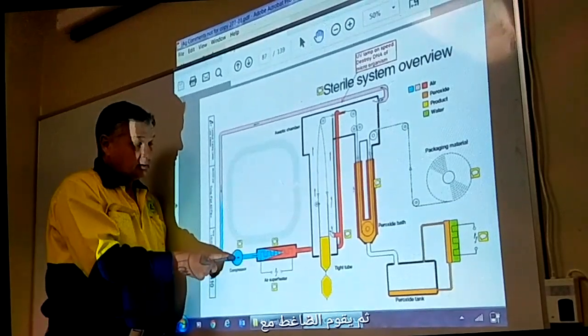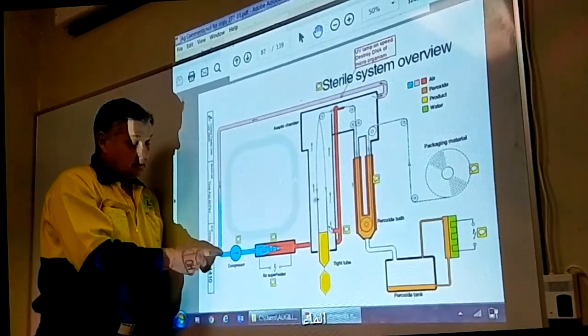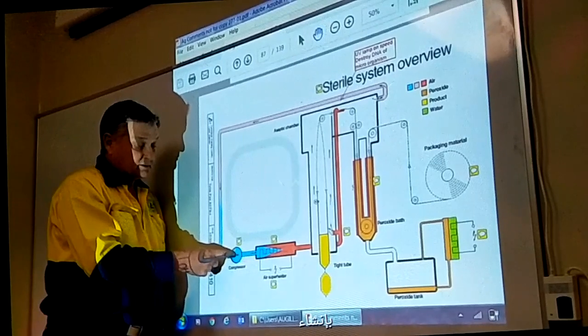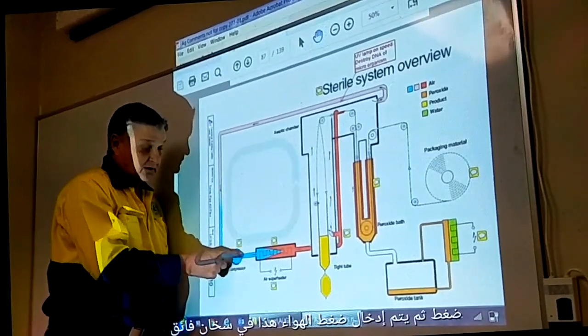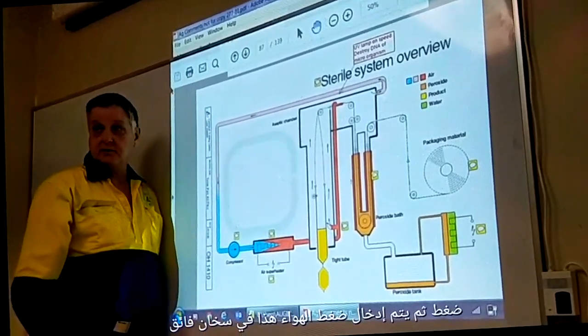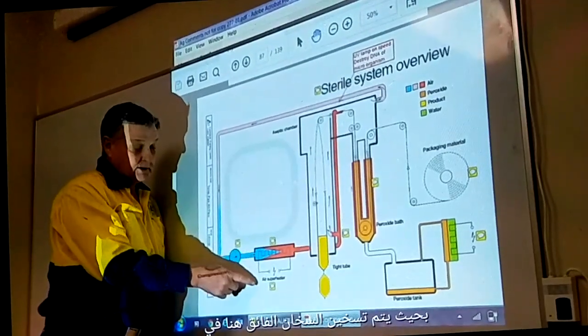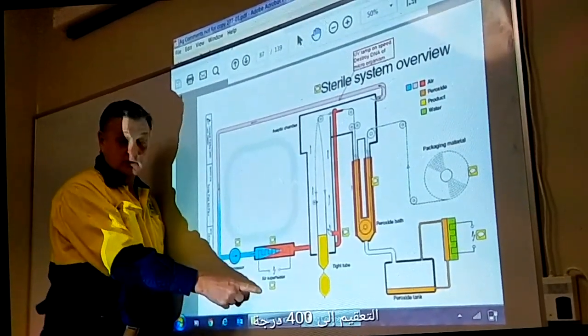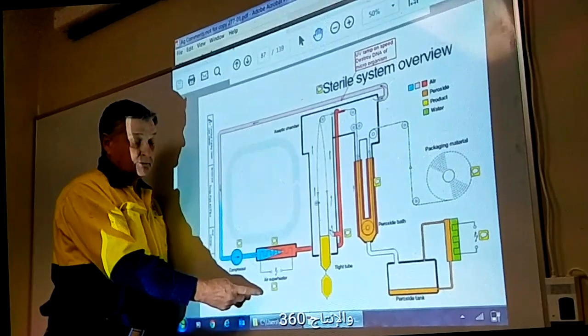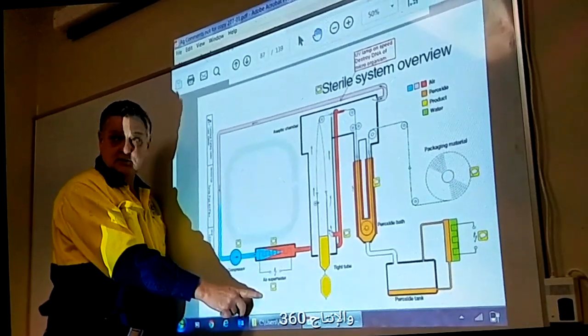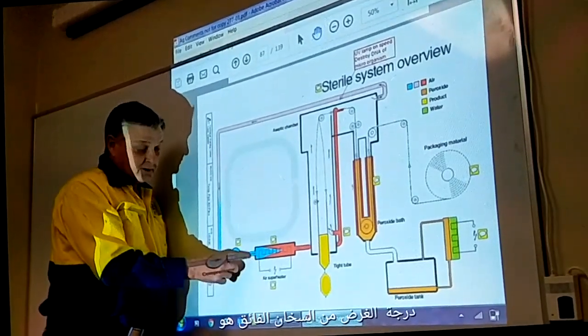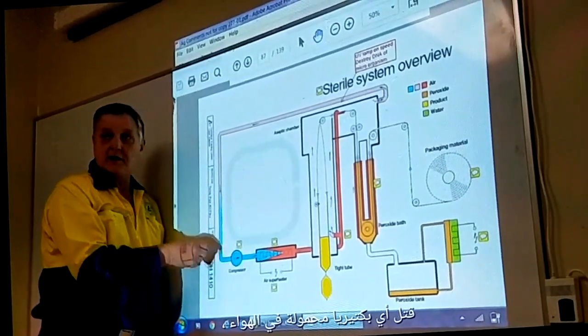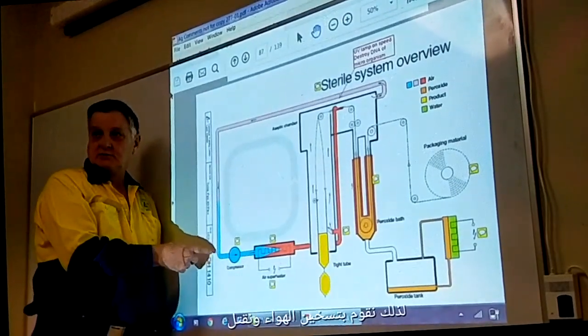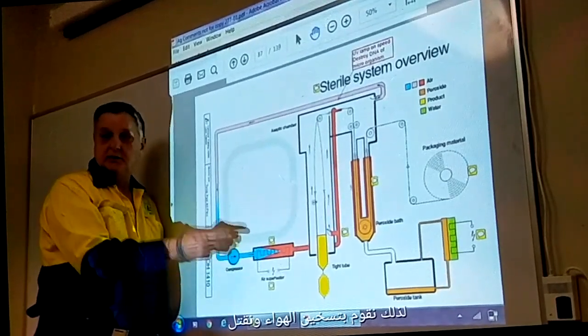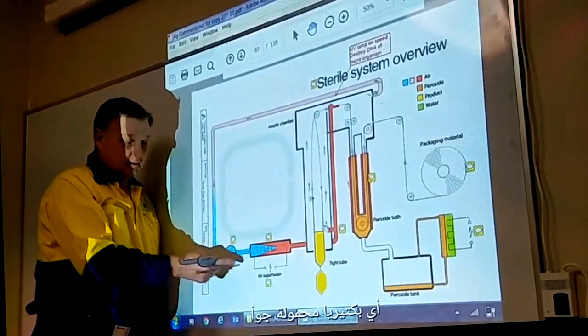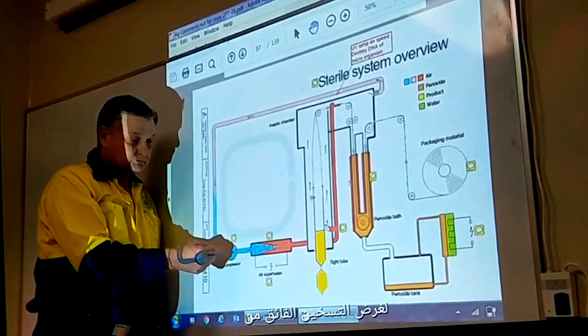So then the compressor, together with water, creates a pressure, and then this air pressure is fed into a superheater. So the superheater here heats up in sterilization to 400 degrees, and the production 360 degrees. The purpose of the superheater is to kill any airborne bacteria. So we heat up the air and we kill any airborne bacteria. So that's the purpose of the superheater.